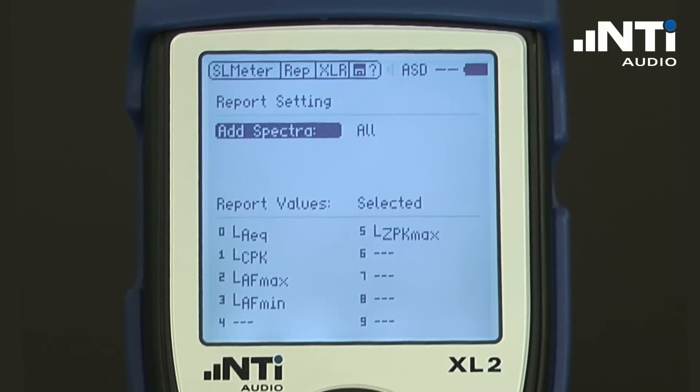We will see that after we have explained the logging functionality. For comprehensive documentation, every measurement can be completed with a voice note recording that is stored together with the measurement results. The user may ask what happened that the LEQ was so high in the last 10 minutes, or what frequency range contributed most to the LEQ. For this purpose, we have implemented the logging feature into the XL2, which writes the desired measurement results during a long measurement period at the defined measurement interval into a file, allowing us to find answers to all these questions.